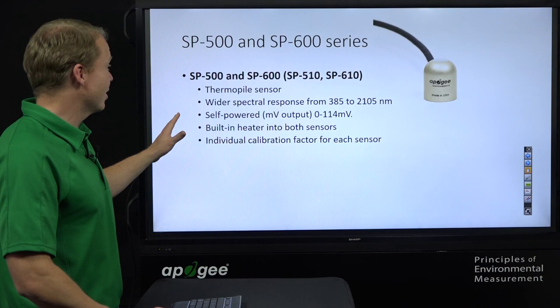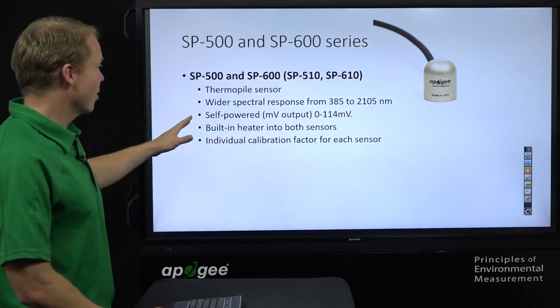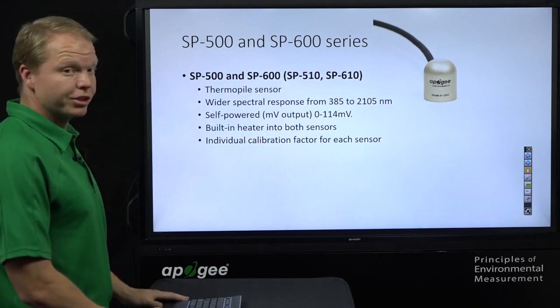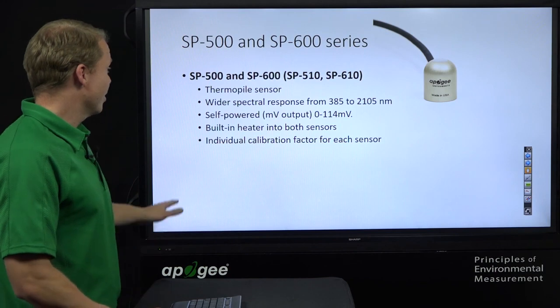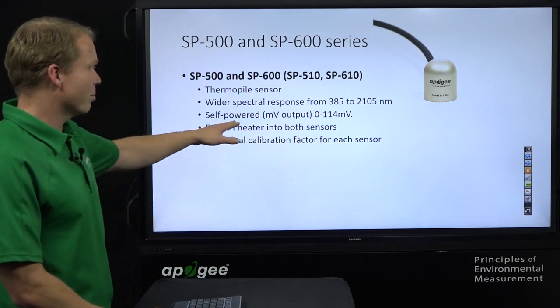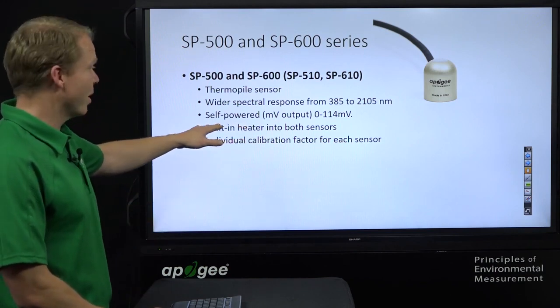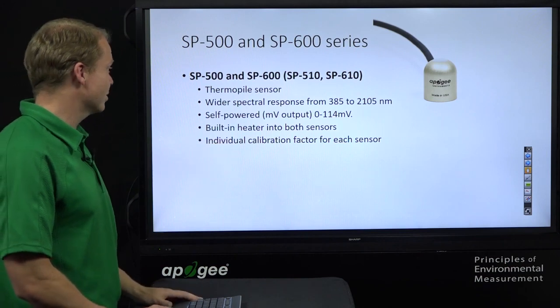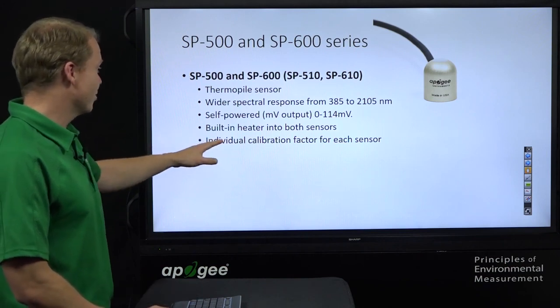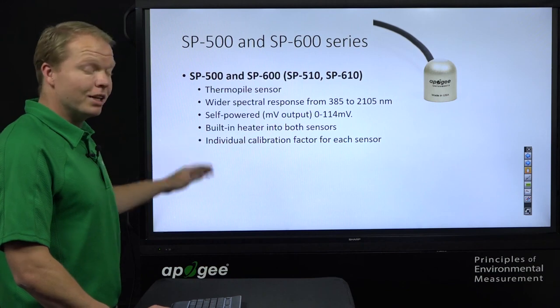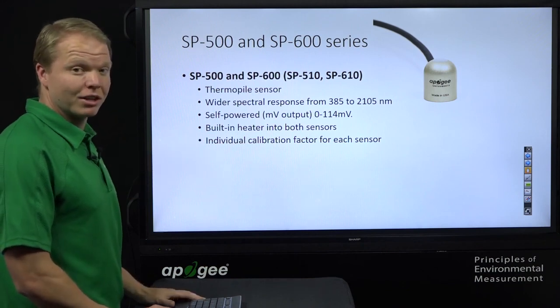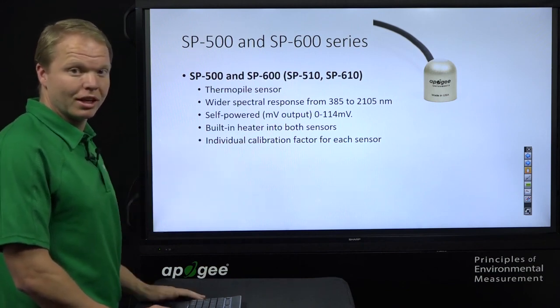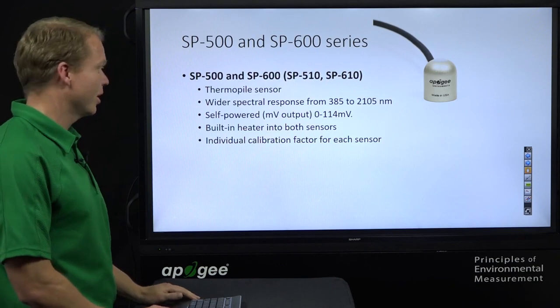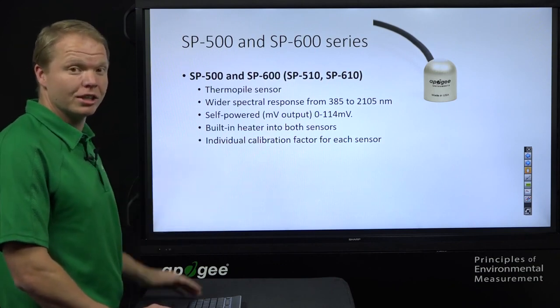The SP500 and SP600 series, these are all thermopile sensors, the larger spectral response. They're self-powered, and so they have a smaller signal than our other self-powered one, 0 to 114 millivolts. Built-in heater in both sensors. And then each one does have an individual calibration factor, so they are not interchangeable like the SP100 and 200 series. If you change the sensor, you do need to change the calibration factor as well.